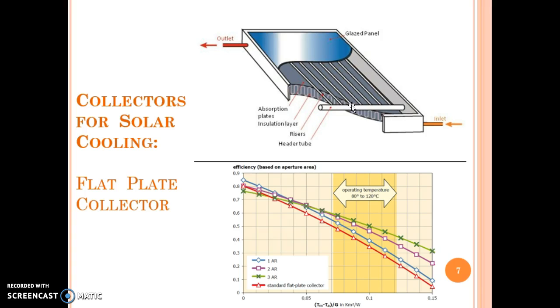And this shows how the collector efficiency decreases as you have more and more temperature difference between the liquid outlet and the ambient temperature. If you use better anti-reflective (AR) coating on the glass, then you can expect better efficiency. And if you use more number of glasses, the efficiency will go on increasing, particularly at higher temperature differences, but obviously this will also increase the costs.